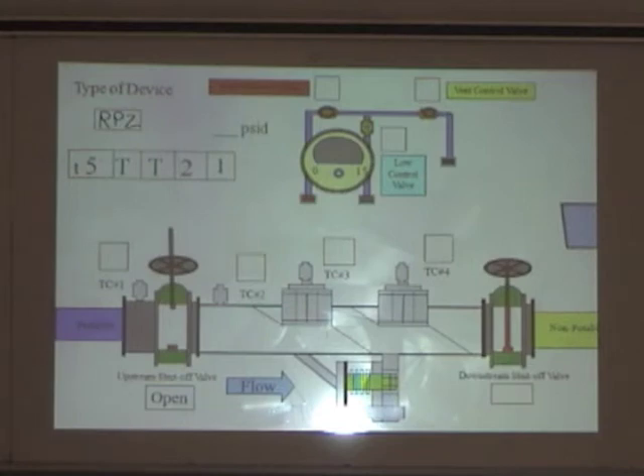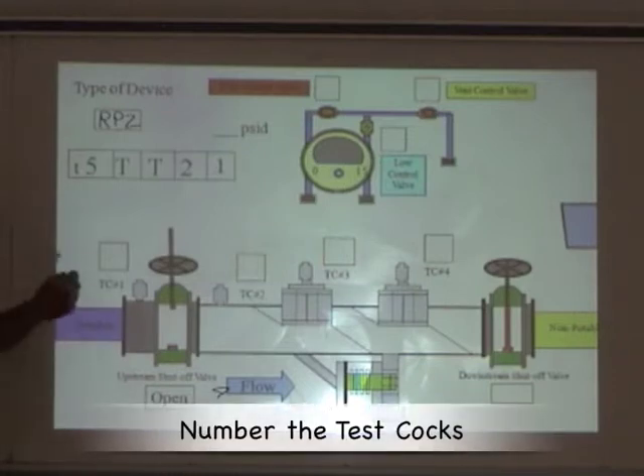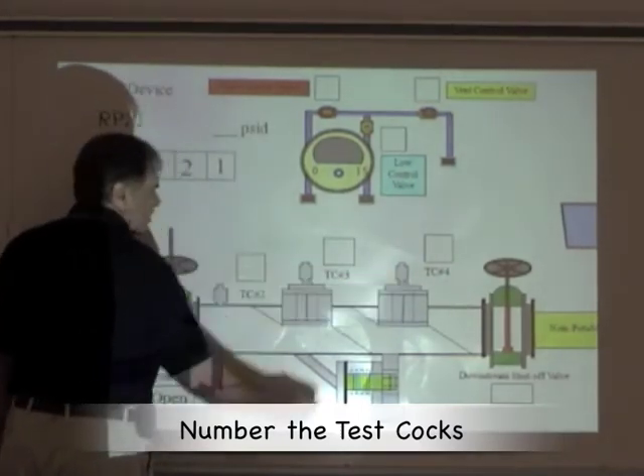The next step is to determine the direction of flow — we look for the arrow. Next step is to number our test stops: test cock number one, two, three, and four. How do we know that's test cock number four? The arrow is pointing to it. Test stop number one is located on the upstream side of the upstream shutoff valve.